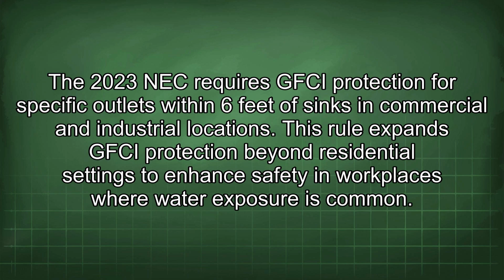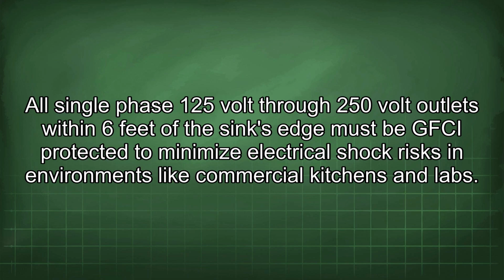The 2023 NEC requires GFCI protection for specific outlets within 6 feet of sinks in commercial and industrial locations. This rule expands GFCI protection beyond residential settings to enhance safety in workplaces where water exposure is common. All single-phase 125V through 250V outlets within 6 feet of the sink's edge must be GFCI protected to minimize electrical shock risks in environments like commercial kitchens and labs.